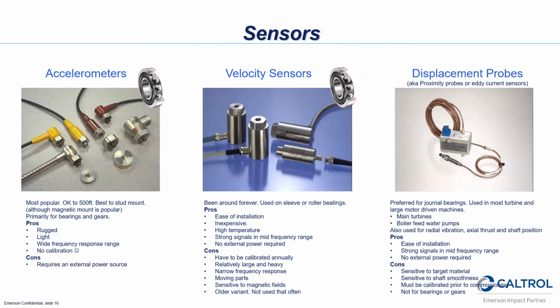These are the different types of sensors that we use for gathering the vibration data. Velocity sensors are pretty much obsolete. You don't find those anymore, because the standard accelerometer covers all the low frequency range, high frequency range, and bearing defect faults. They've advanced so much that velocity sensors have become obsolete because they will not get high frequency ranges. They do have their place in the industry, but I can't remember the last time I've seen one. So pretty much everything is measured with accelerometers, and that would be through a contact through a ball bearing, because we're picking up waves through the contact of that bearing.